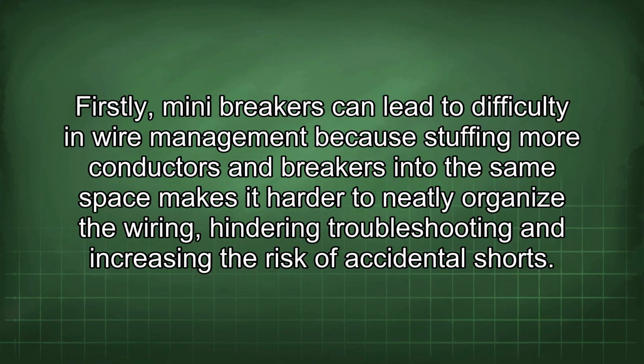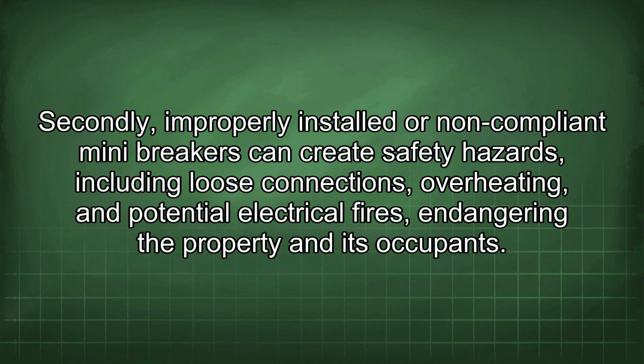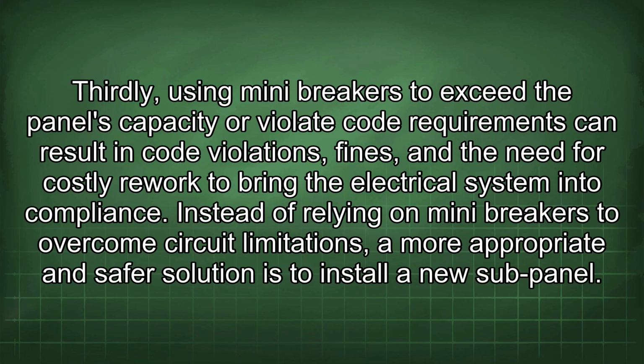Firstly, mini breakers can lead to difficulty in wire management because stuffing more conductors and breakers into the same space makes it harder to neatly organize the wiring, hindering troubleshooting and increasing the risk of accidental shorts. Secondly, improperly installed or non-compliant mini breakers can create safety hazards, including loose connections, overheating, and potential electrical fires, endangering the property and its occupants. Thirdly, using mini breakers to exceed the panel's capacity or violate code requirements can result in code violations, fines, and the need for costly rework to bring the electrical system into compliance.